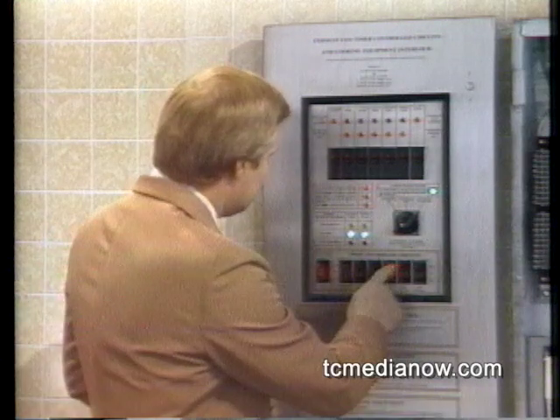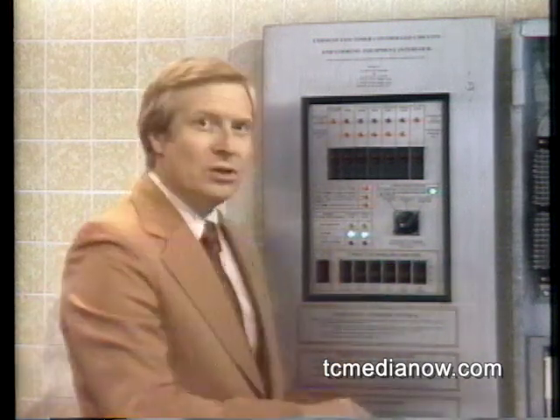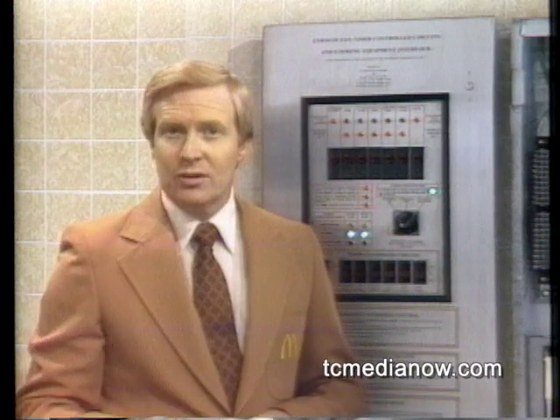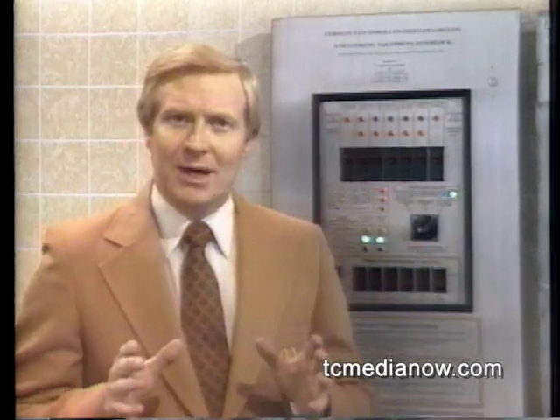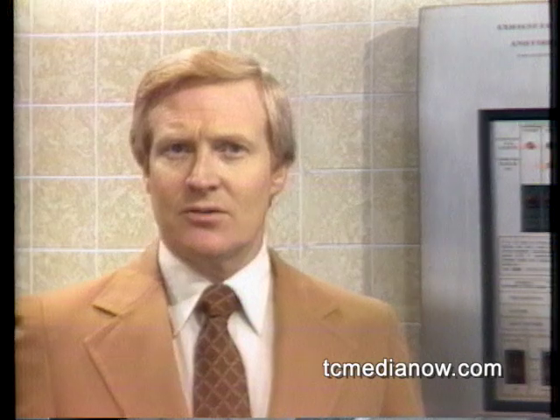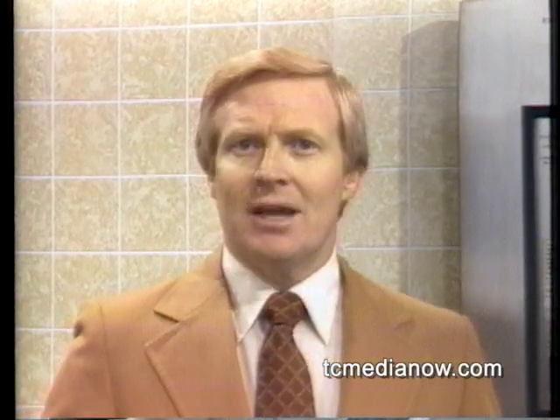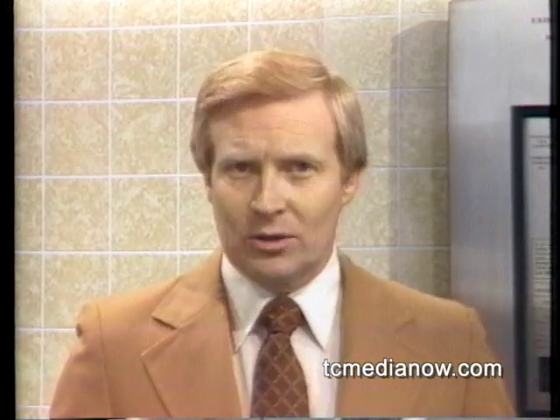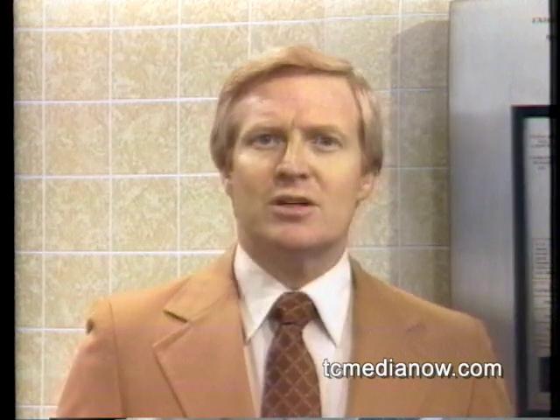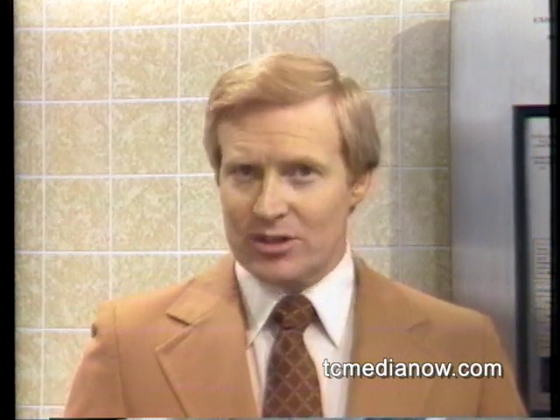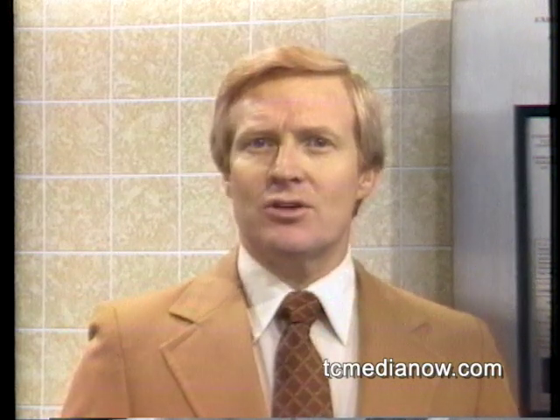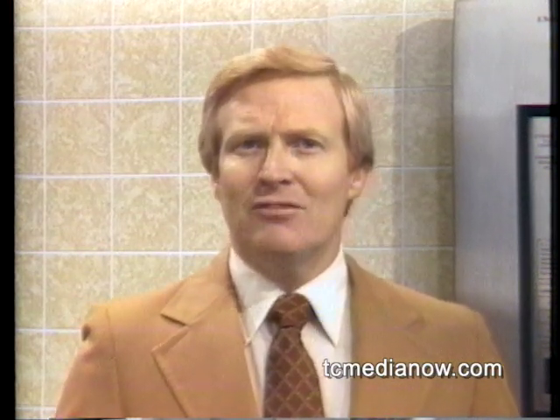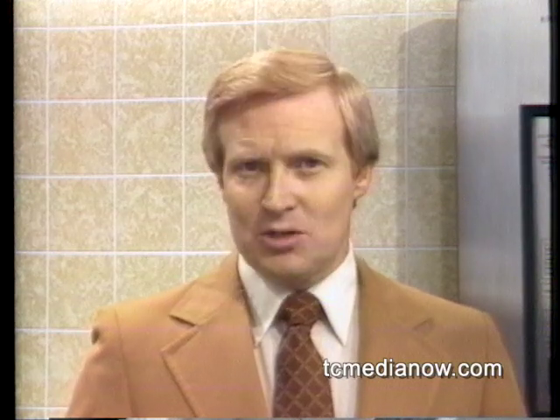When all switches are in the auto position, the photocell on the roof automatically controls exterior lights according to programmed time cues. Now, some older clock panels do not have thumb wheels for setting the store's opening and closing times. These panels do not include the auto load feature, and all control points must be programmed individually, as just described, according to the times listed on the chart inside the panel cover. Full programming instructions are furnished with each panel.